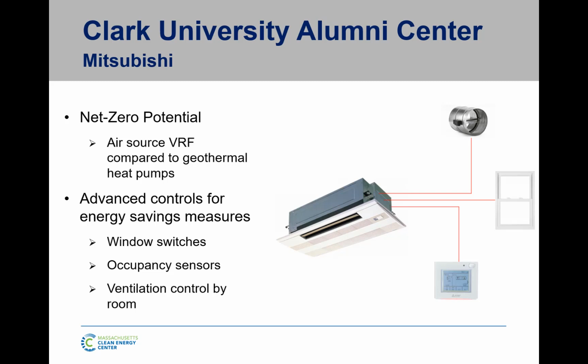We took a similar method with this, except we didn't automate the windows. All we did was monitor the conditions, and we alert the end user with a green light when it's beneficial to open their window. So they still have to do it themselves. It gives them the option, but it tells them it'd be wise to open the window now and get free cooling. So they go and open the window, cooling shuts off at the fan coil, and ventilation shuts off at the fan coil. So all stuff that's fairly easy to do with the equipment that's built into the VRF system.